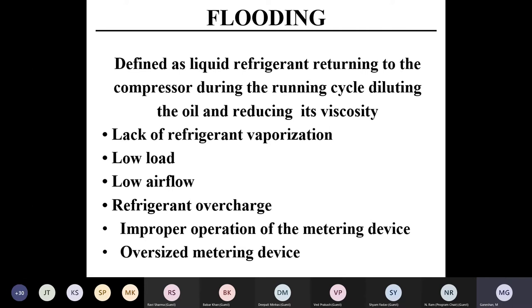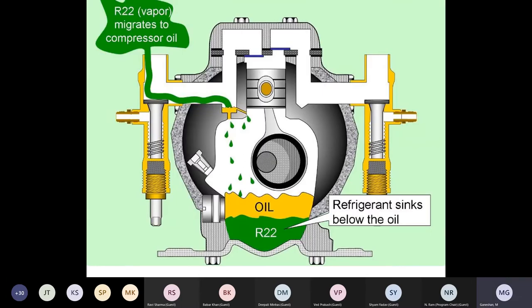Then refrigerant overcharge. Sometimes people, without understanding, without checking, even overcharge can lead to liquid returning back into the compressor. Then an improper or oversized metering device, everything can cause liquid flooding back. Here I am asking, when the liquid keeps on flooding, liquid keeps coming, what will happen? Refrigerant has higher density, so it will always go and settle below the oil.